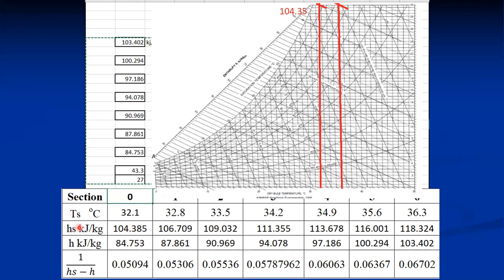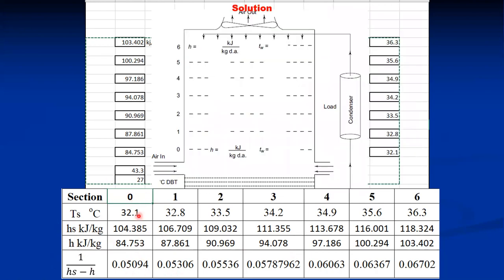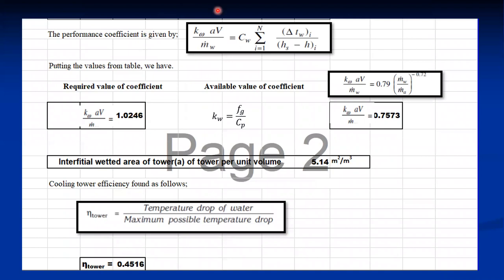With the Hs and H values at each section, we calculate 1/(Hs − H) for each section — using the average of values at the boundaries for each section. There are six values of 1/(Hs − H), one per section. As per the definition of the demand value of performance coefficient: Kw × A × V / M_dot_W = Cw × Σ[ΔTw / (Hs − H)] for each section. With ΔTw = 0.7 for each section and the six computed values of 1/(Hs − H), we calculate the required performance coefficient (demand value).